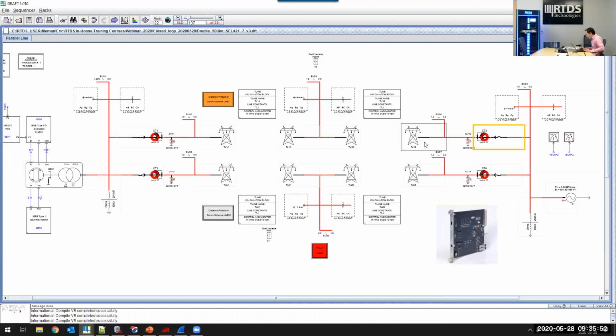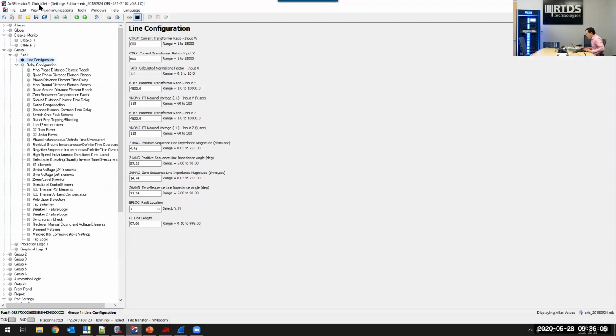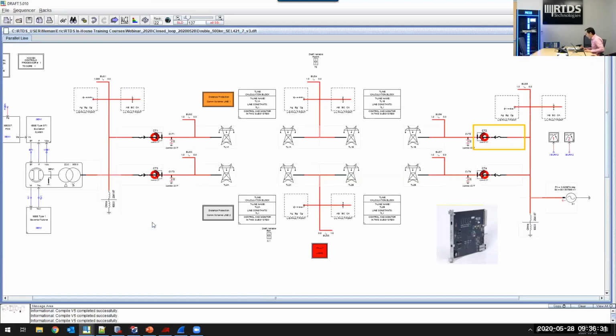Okay, so next let's have a quick look at the relay settings. There are 2 software tools from the vendor that need to be used for configuring the relay for IEC 61850 applications. The QuickSet is one of them. In this demo, this tool is used to set the line parameters, CT-PT ratios. Now the length of the protected line is 97 kilometers here. By the way, the line impedance data can be obtained from draft by viewing a file called map file after the draft is successfully compiled. So we can go here and view map file.